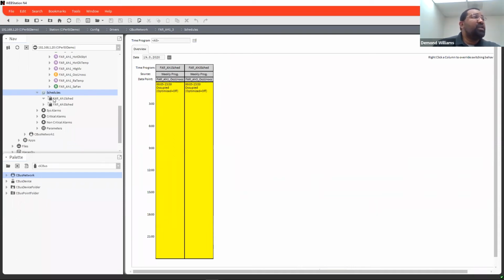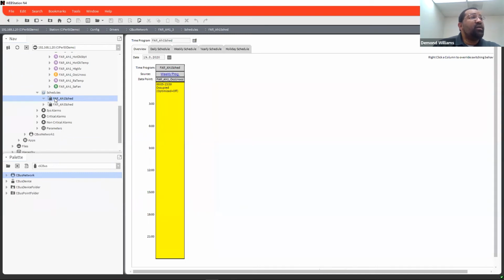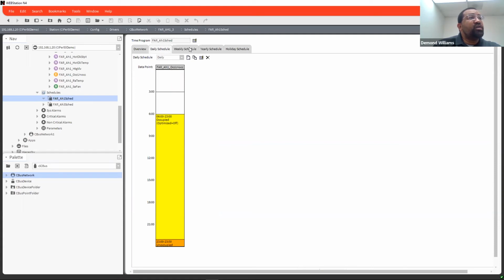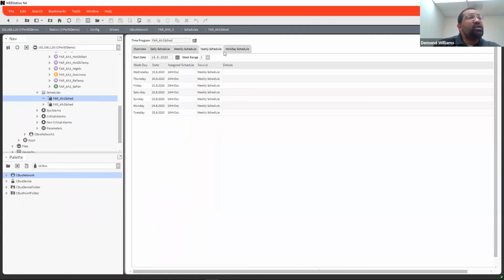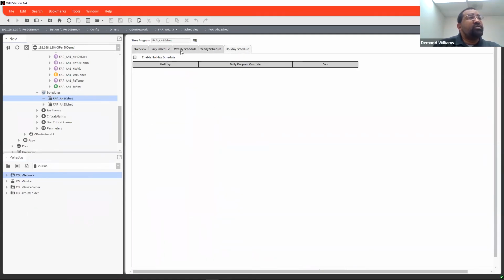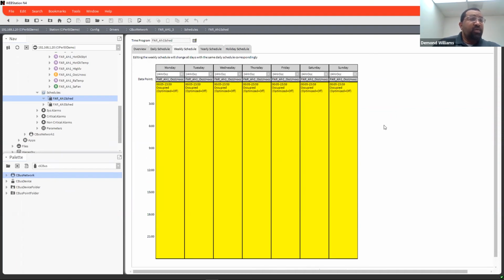So clicking here on each individual one, now I can see the overview. I can get to daily schedules, weekly schedules, yearly schedules, and then holiday schedules if there were any in there. The way Honeywell used to do it is they would create a day schedule and then assign that day schedule to a weekly schedule. And it's just like Niagara where you can actually push and pull your schedules as well.